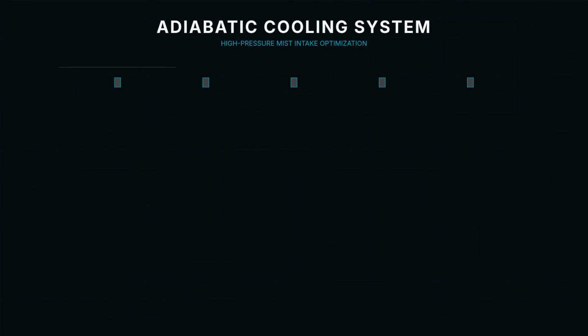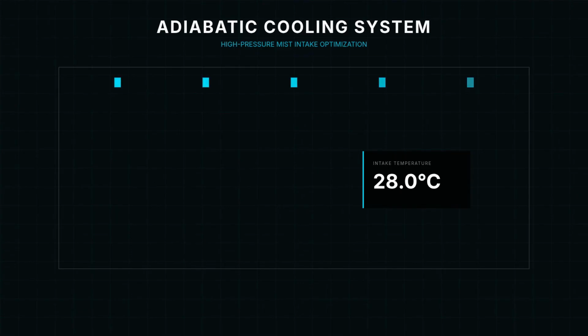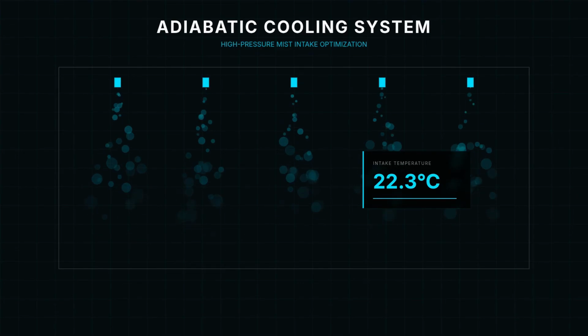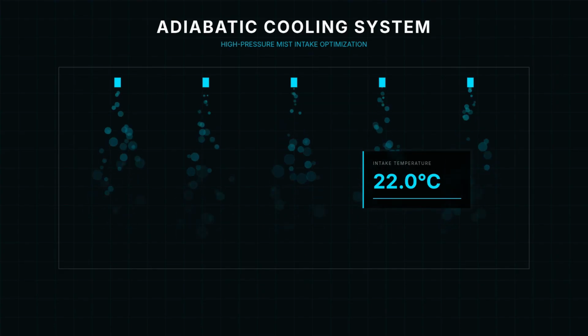Adiabatic cooling uses water evaporation to reduce air temperature, the same physical principle as human sweating. No compressors are needed, no refrigeration, just the raw power of phase change. A high-pressure misting system reduces the intake temperature on warm days. This simple but effective addition extends our free cooling window by approximately 1,400 hours every single year. Efficiency does come with a water requirement.